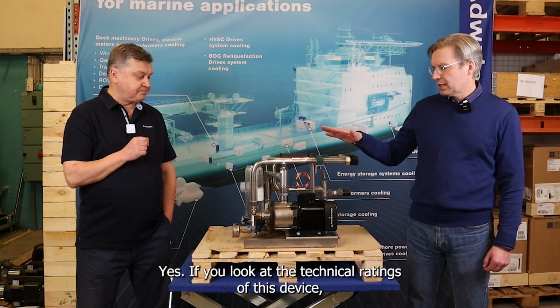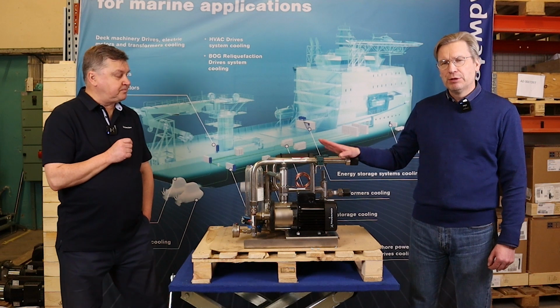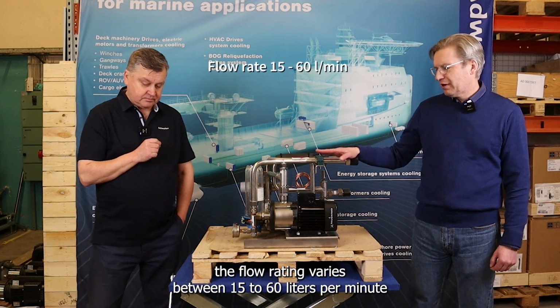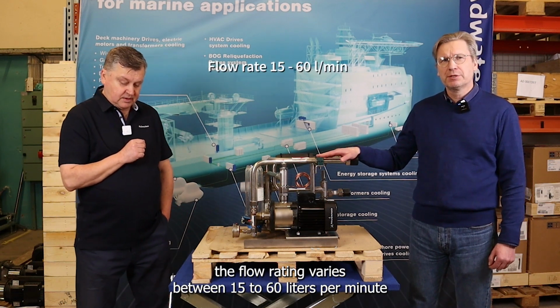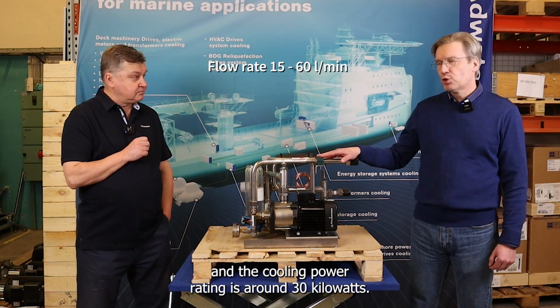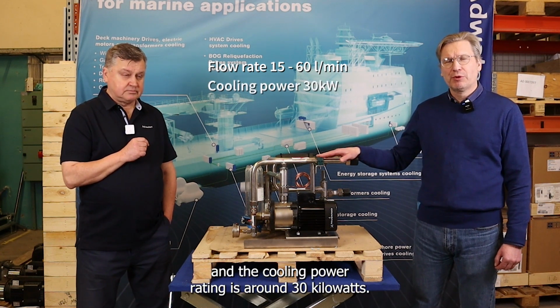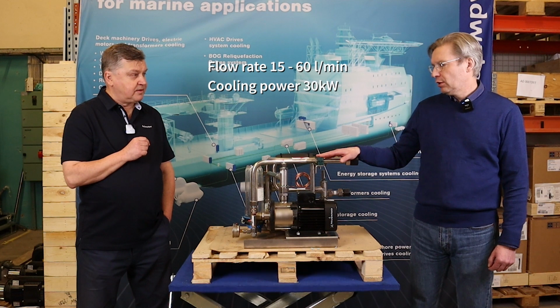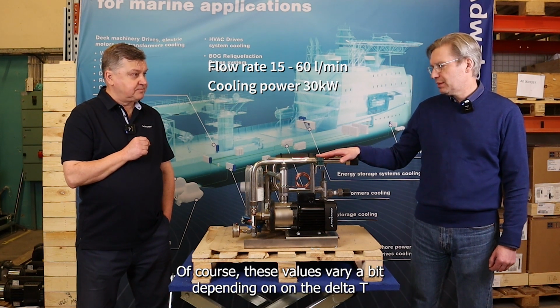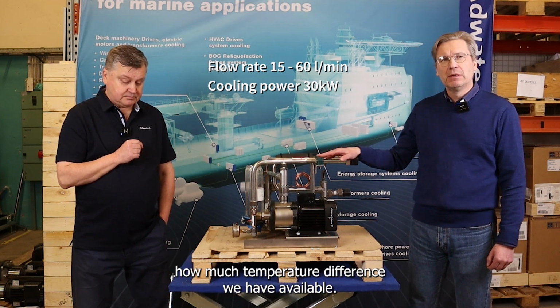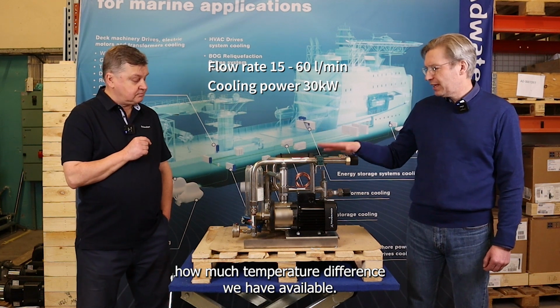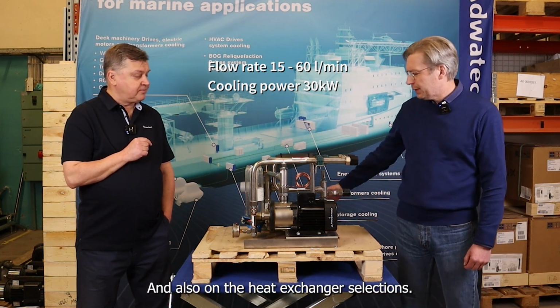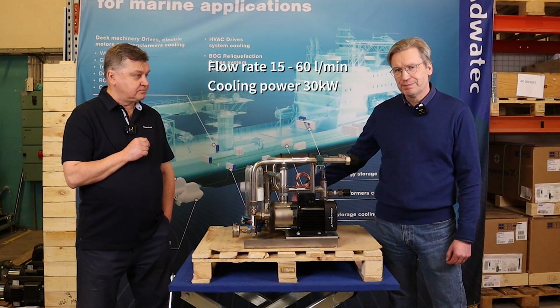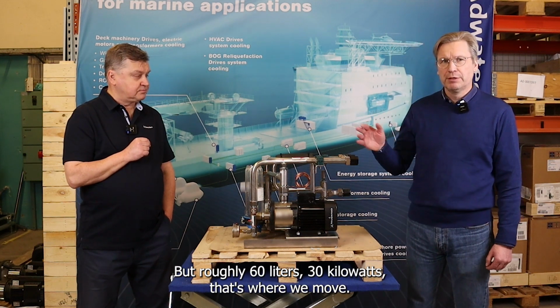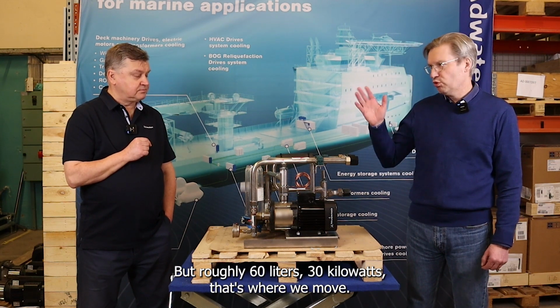If we look at the technical ratings of this device, the flow rating varies between 15 to 60 liters per minute, and the cooling power rating is around 30 kilowatts. Of course, these values vary a bit depending on the delta T, how much temperature difference we have available, and also on the heat exchanger selections. But roughly 60 liters, 30 kilowatts, that's where we move.